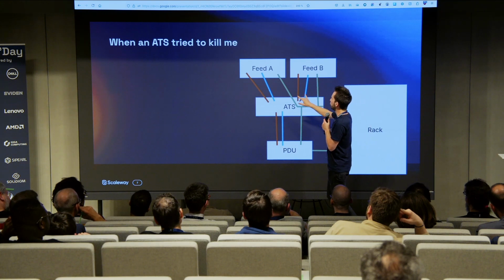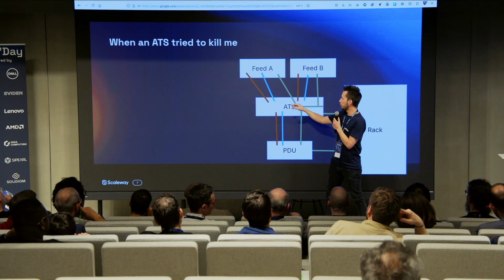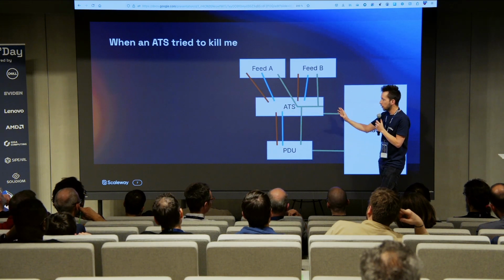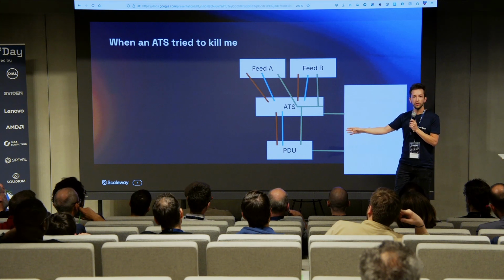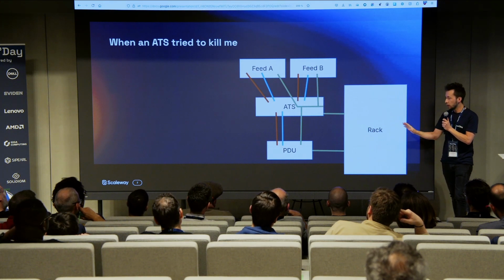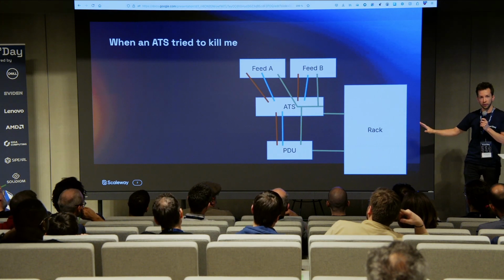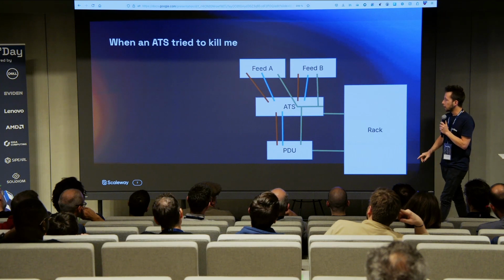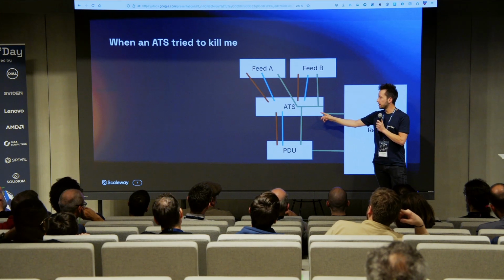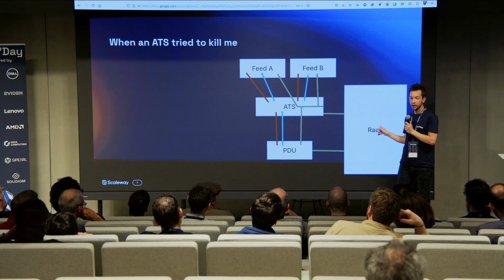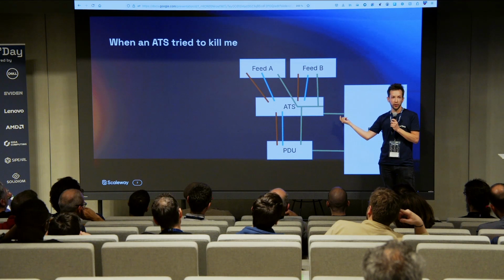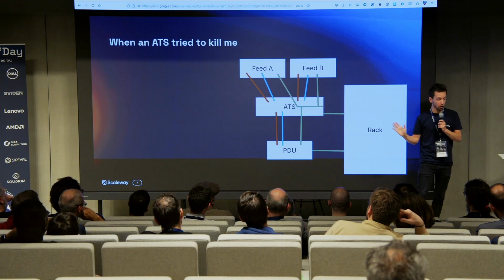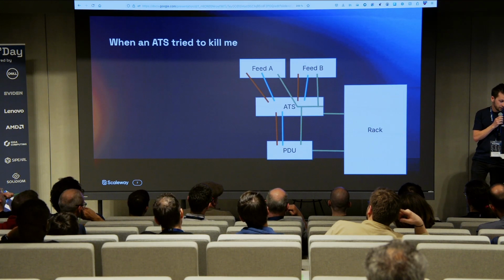Quick diagram: two feeds, phase, neutral, green is Earth, one PDU at the output of the ATS. Really simple. Here, no servers, no power cords, just this. Here, it's because the ATS is racked into the rack, so there is an electrical connection here. No problem. So what happened?